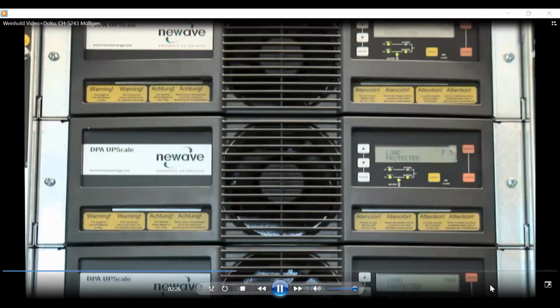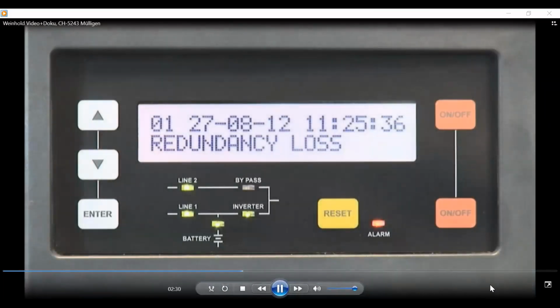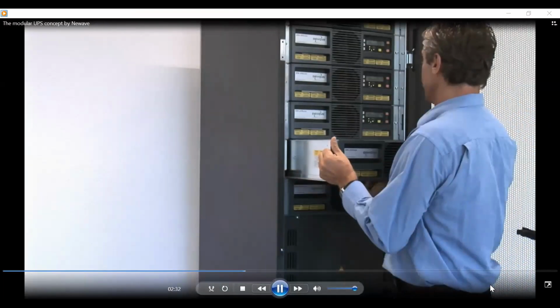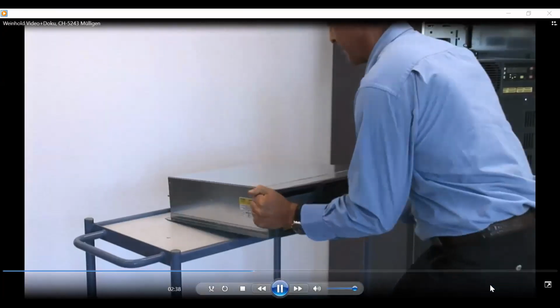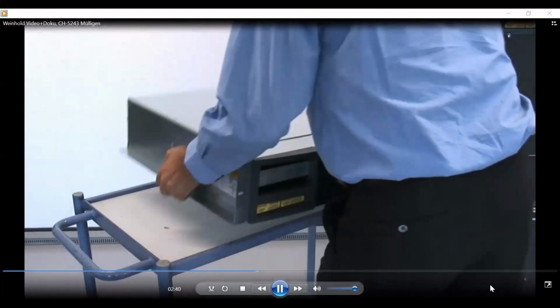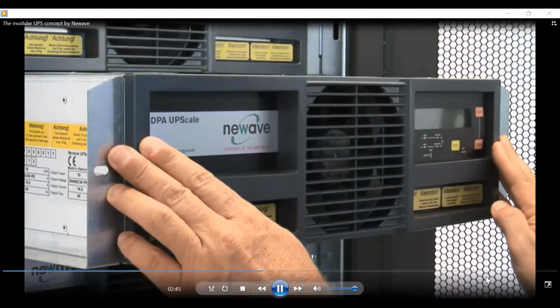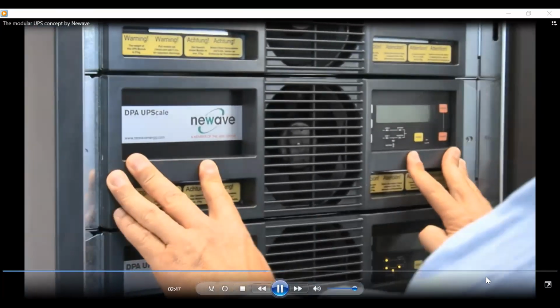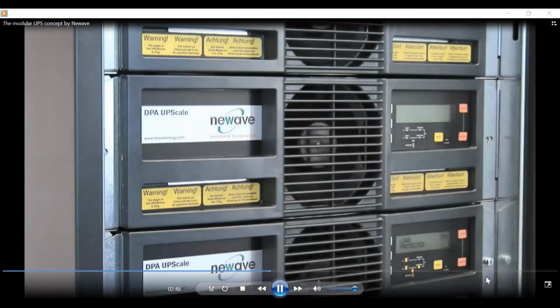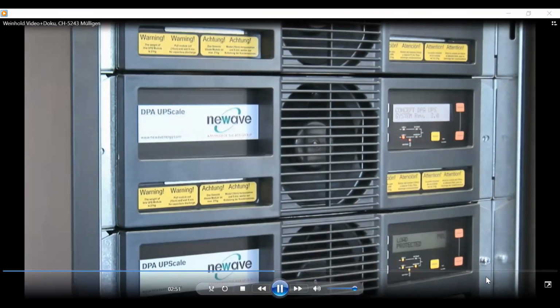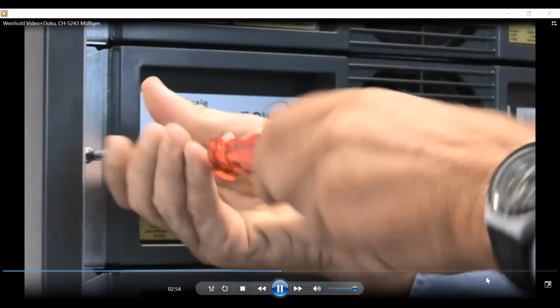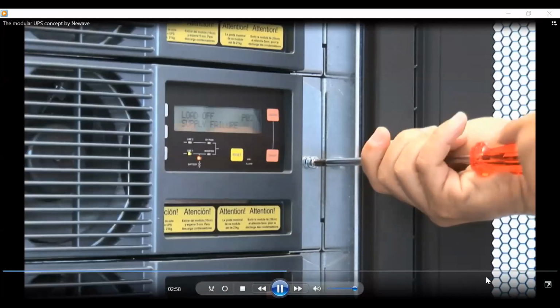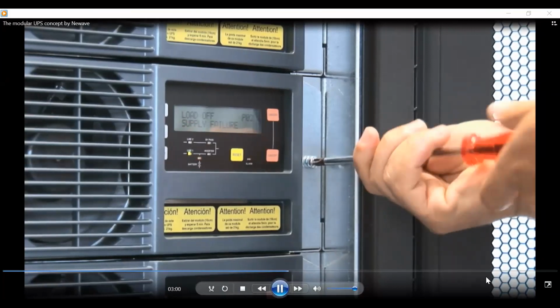If an engineer comes to identify a problem, they can then see which module is defective and replace it with another module. The modules are built in a vertical rack so that they can be easily removed and no rear access is required. With a non-modular UPS system, the mean time to repair could be several hours or more, whereas with a true safe swap modular UPS, the mean time to repair is determined by how long it takes to replace a module, which typically is 15 minutes.